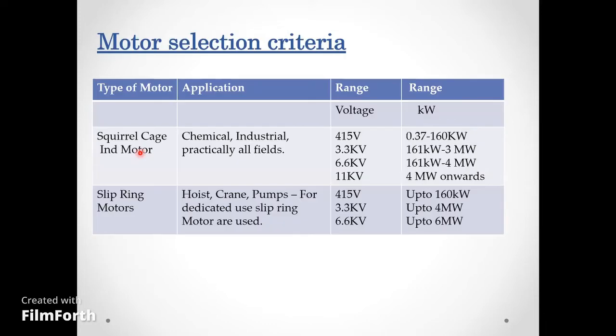In most cases we use squirrel cage motors. Their applications span chemical plants, industrial plants, and practically all fields. The voltage ranges are: 415V for 0.37kW to 160kW; 3.3kV for 160kW to 3MW; 6.6kV for 161kW to 4MW; and from 11kV onwards for 4MW and above.